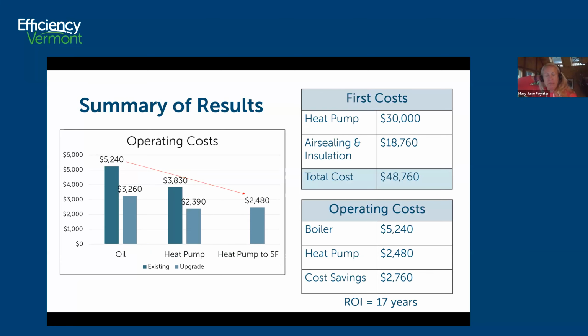And that might be a little bit hard to swallow, but remember, we're starting with a really small amount of oil usage, only 1,500 gallons. And that's where I bring up the question of, could you do air sealing and insulating and do good thermostats and add in ventilation? And then at the end of the boiler's life, you could put in an air to water heat pump. There's other options out there besides going all the way right away to heat pumps. So I want people to think strategically about those options.